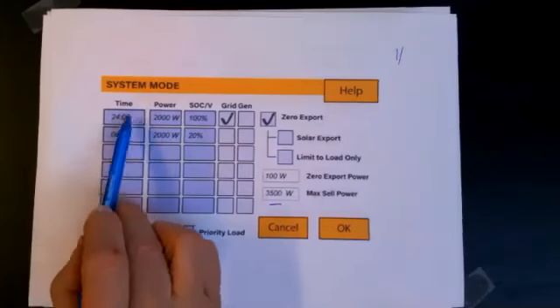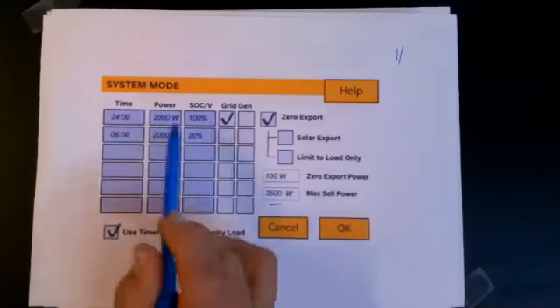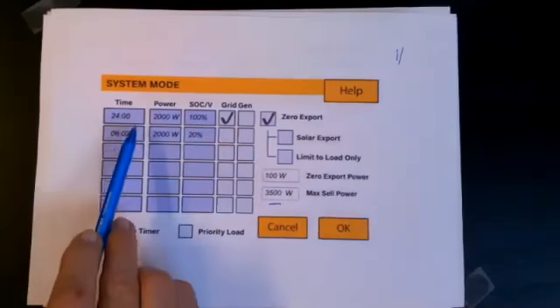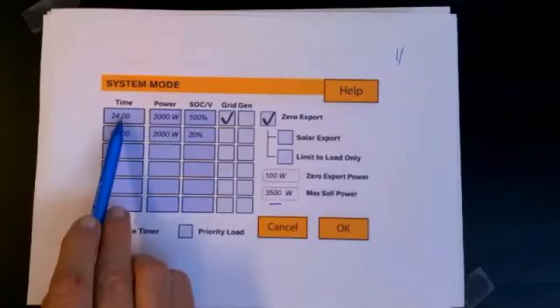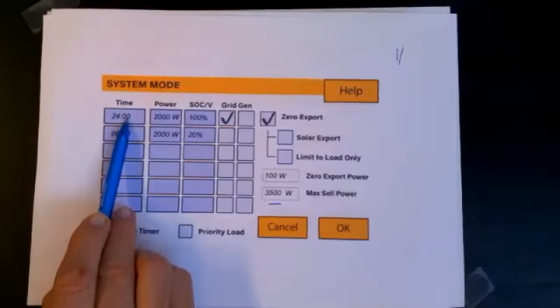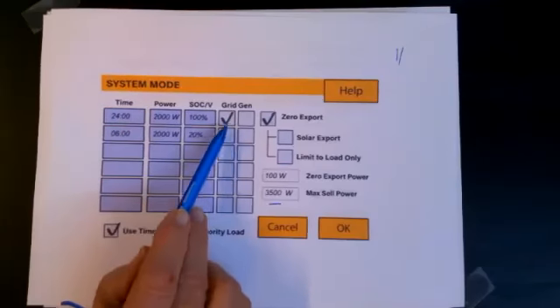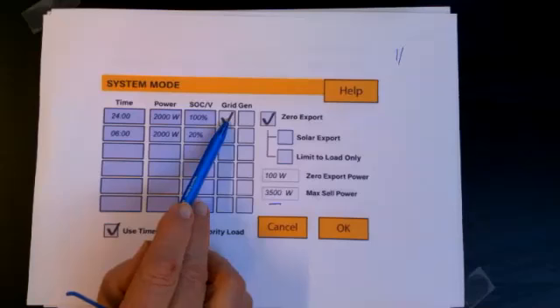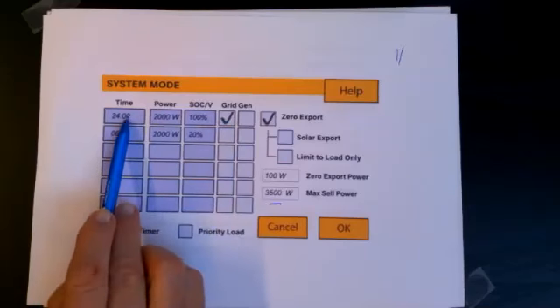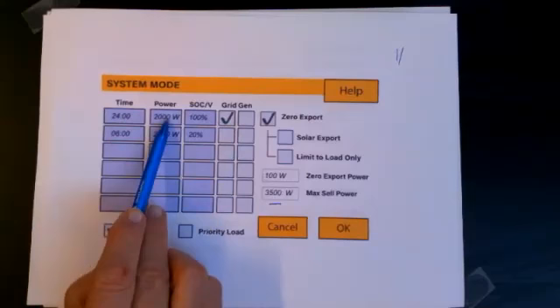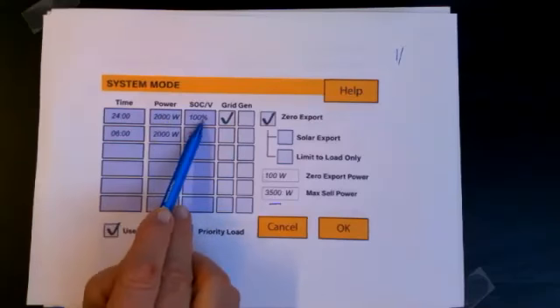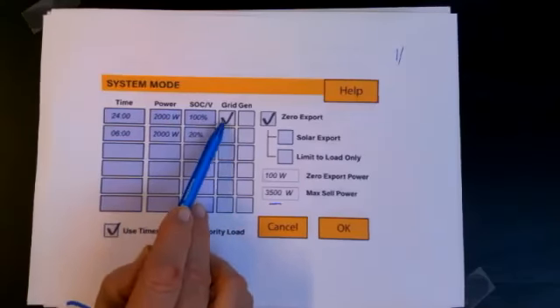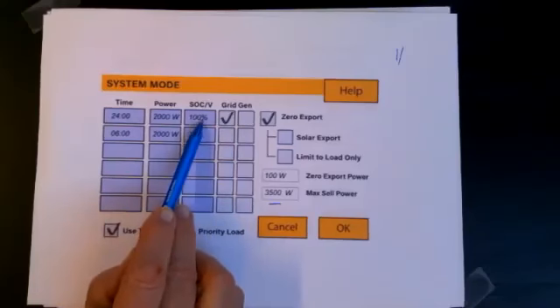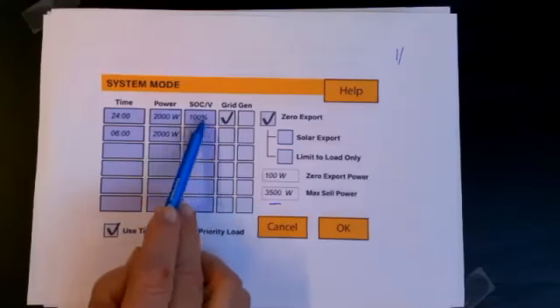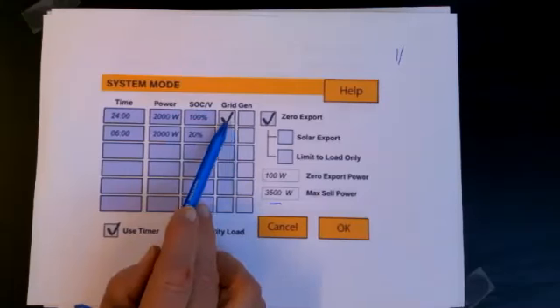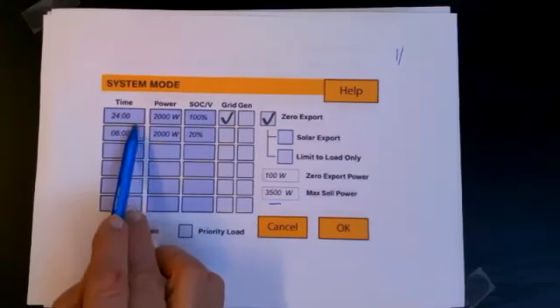So carrying on, the timer here. Use timer. This is real time. So basically you set the time, and this is when it will activate. If you don't put any tick in here, it will switch off at that time. So on here at 24, at midnight, the power is 2000 watts, and I want the grid to charge my battery to 100%. That's just an example. So at midnight, I want it to charge to 100%, and I can click here, and it will take it to 100%.